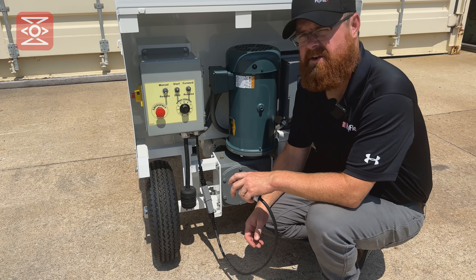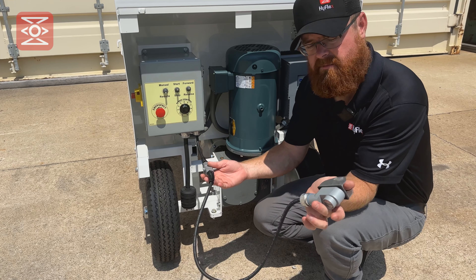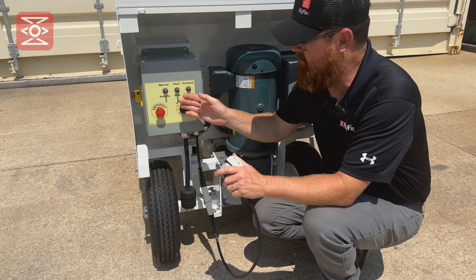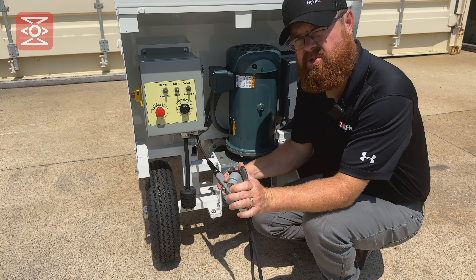If you're experiencing problems with the HC-30E randomly turning on and off, the problem could lie in the remote switch. To eliminate the remote from the problem, operate the machine in manual. If the problem goes away, the problem could be in the remote switch line itself.